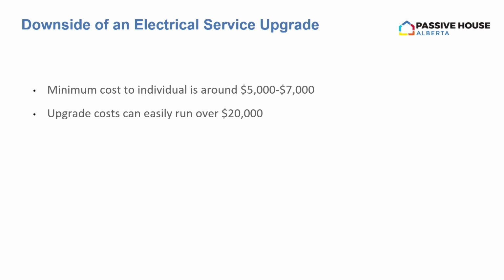First of all, we want to avoid that cost. Depending on how fast, whether you're the first on the block to upgrade to a 200 amp service, it's still going to be either $5,000 to $7,000, and that's if the transformer is close by, the transformer has capacity, and you have an overhead electrical line. If you have an underground line or the transformer is full, it can very quickly get into the $20,000 or plus range for that upgrade, and then generally electrification just dies right there.